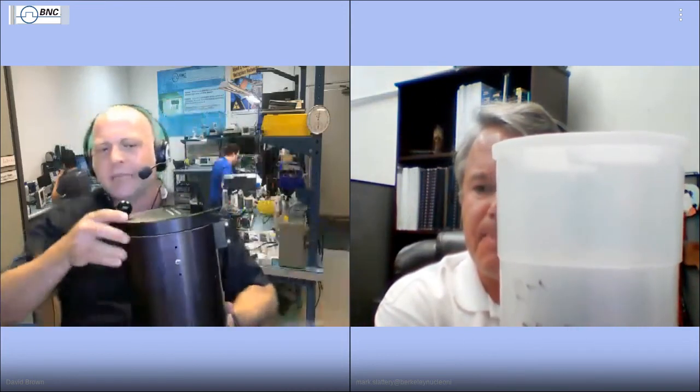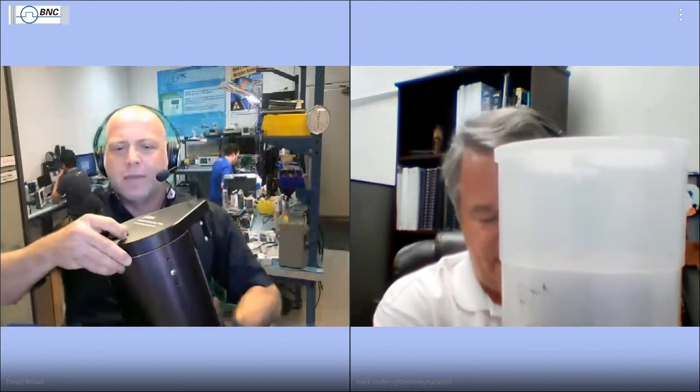And then I've got the shield to get rid of the background in that same setup, right? So you would put that entire Marinelli beaker and detector in the shield. That is very important. If we're testing materials that we expect to be very low activity, we'd want to test it someplace that has very low background. So we'd place the detector inside the shield, put the Marinelli beaker on top, and then close the lid. It swivels open, swivels closed. This is quite common for soil sample remediation type activities.